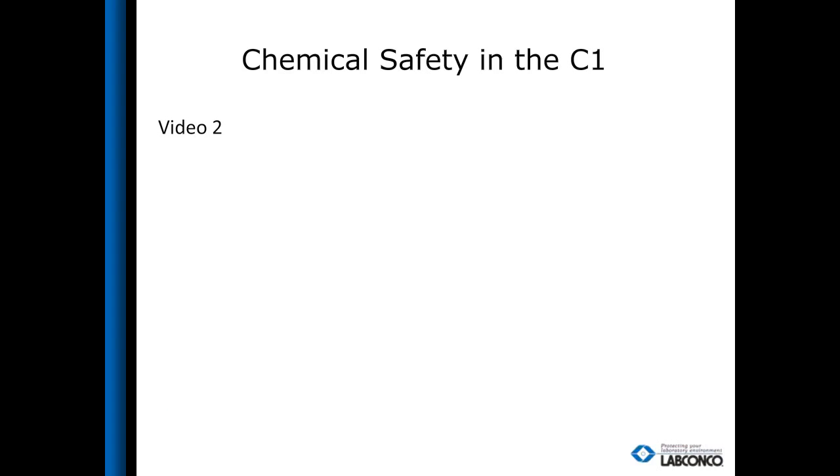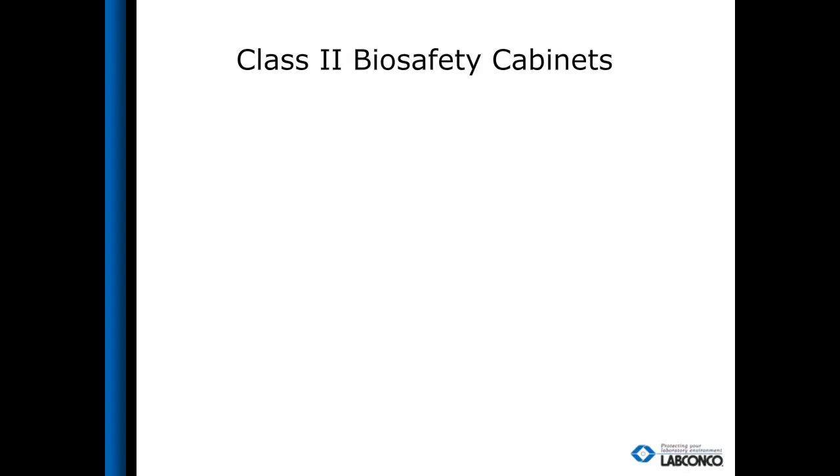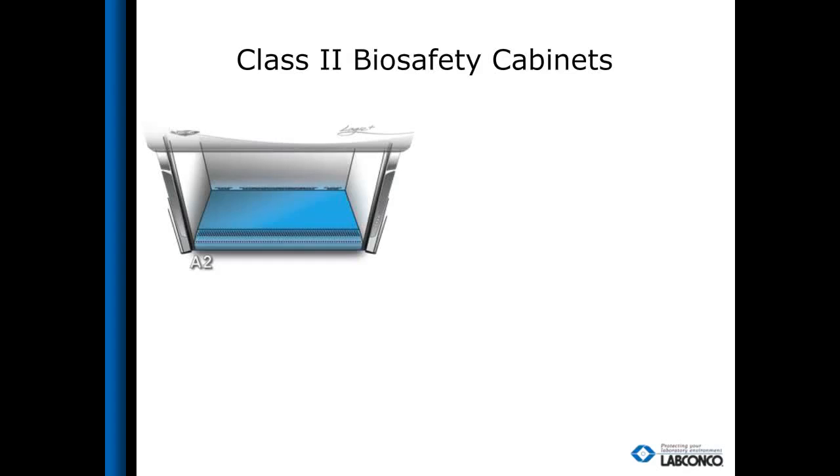So in this next video, if you take a chance to watch it, it shows how that chemical safety is achieved. By generating two internal but independent airflow systems within the cabinet, you're able to basically split the air that's being moved and provide a single pass airflow for your chemical-laden air, which also makes it a lot easier for training users, and this is where the safety comes in for certain.